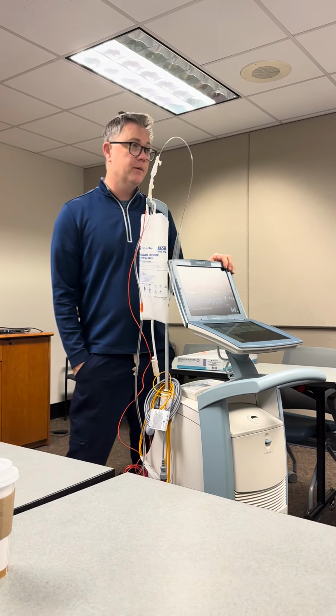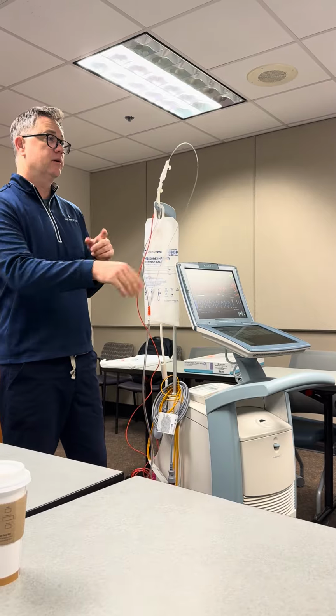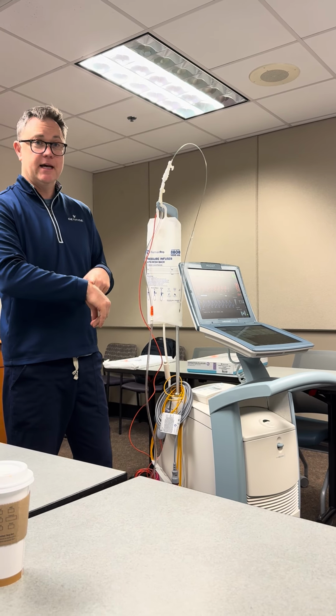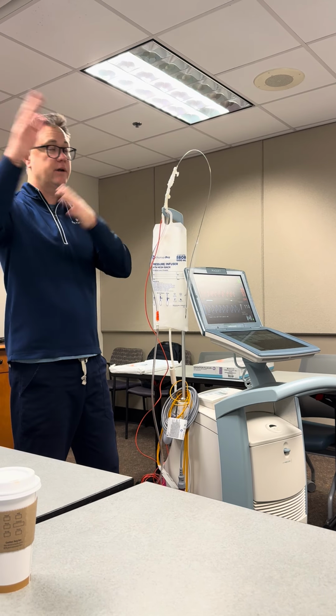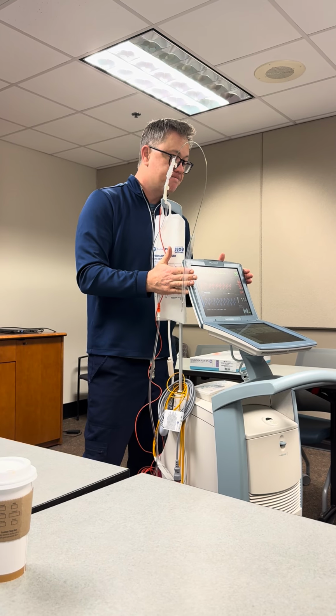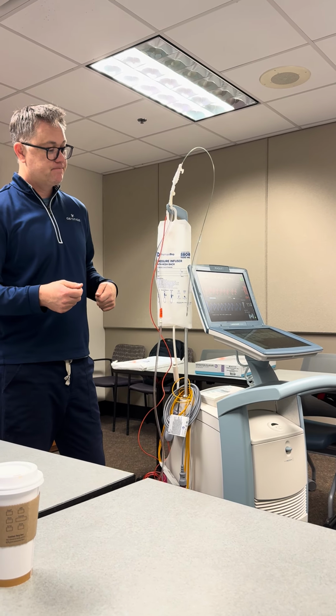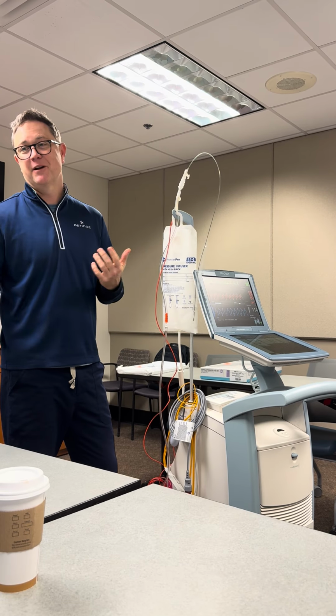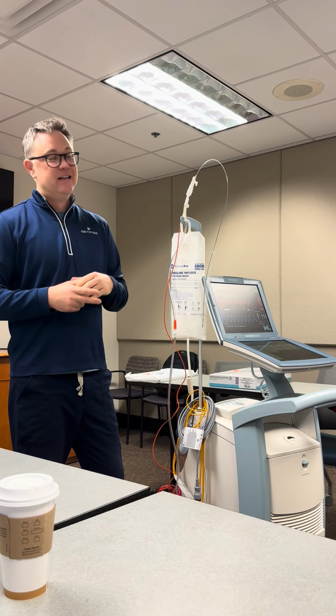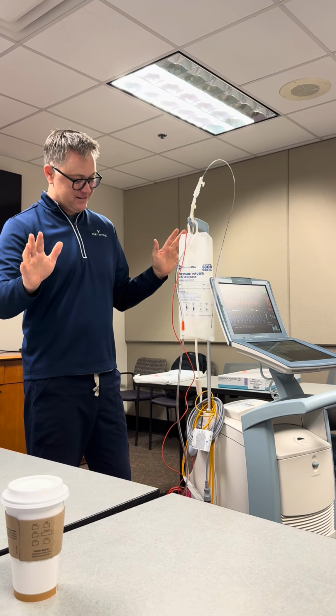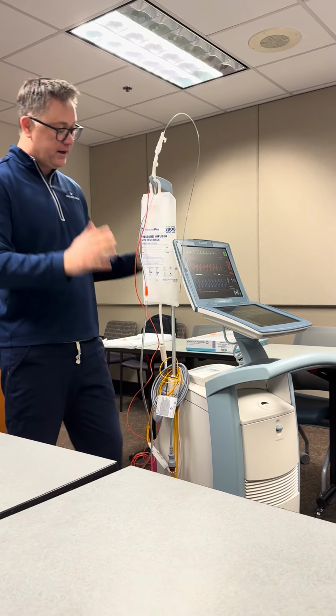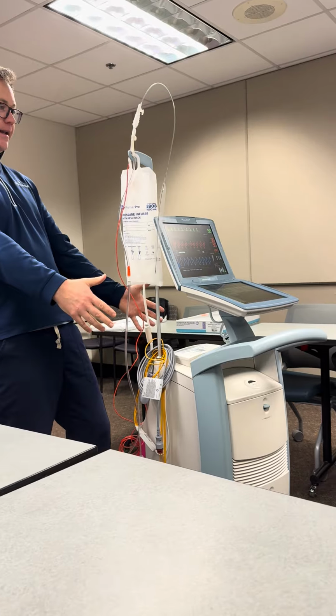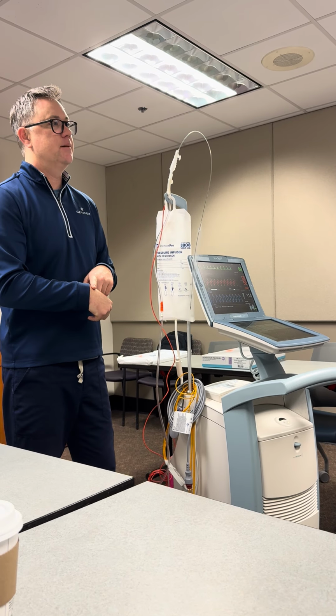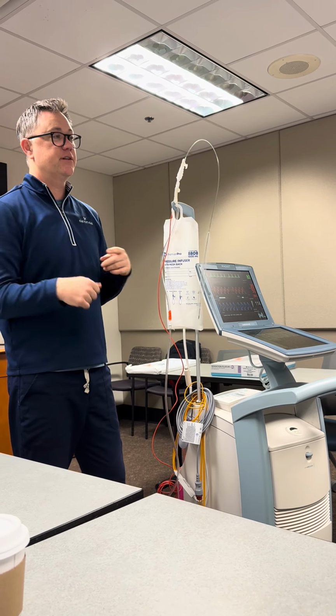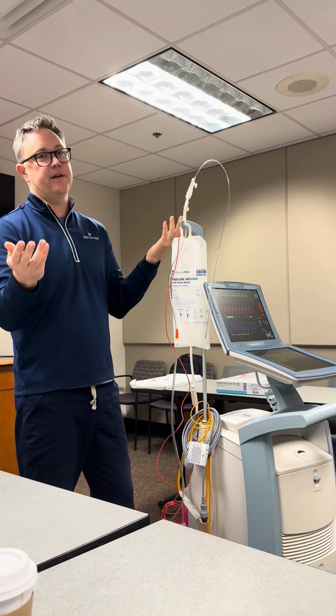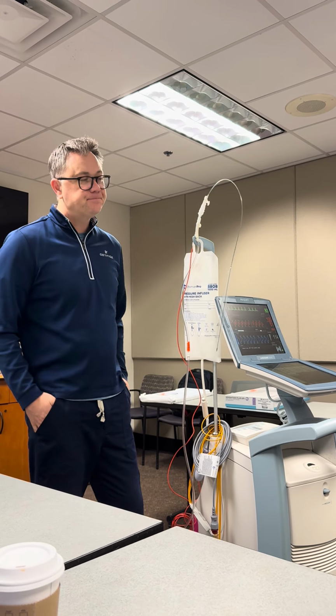If you're on a transport, the hard part is that once you notice you potentially have a ruptured balloon, we're going to ask you to monitor that time so that you can let them know when you arrive at whatever facility. Obviously, you want to get to the closest facility you can. They're going to have to make a decision. Well, if it's a ruptured balloon, you're going to have to pull it anyway. I was thinking of a catastrophic failure. To complicate things, if you were on a transport with this machine and for some reason you had a catastrophic failure and the machine shut down, we're going to ask you to time that as you are on your way to the next facility, because they're going to have to decide whether to pull that catheter out or continue therapy, based on how long it's been in there.